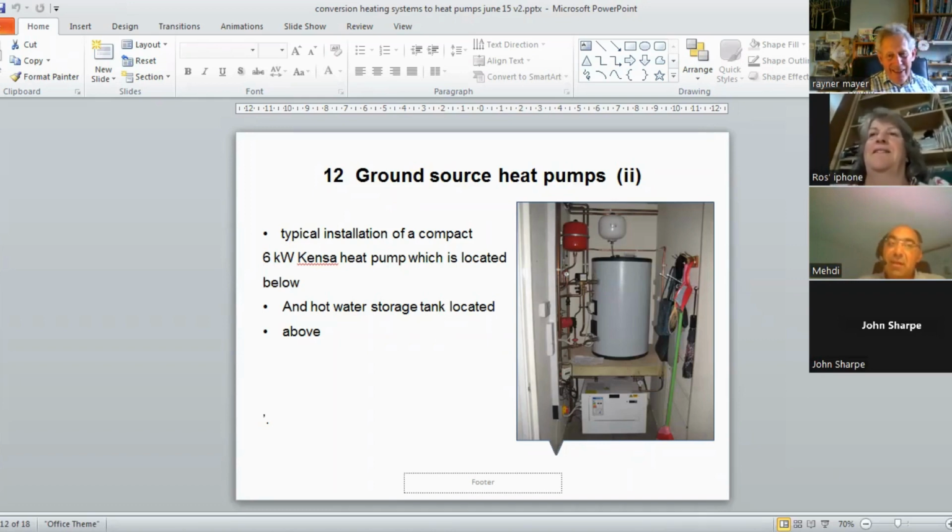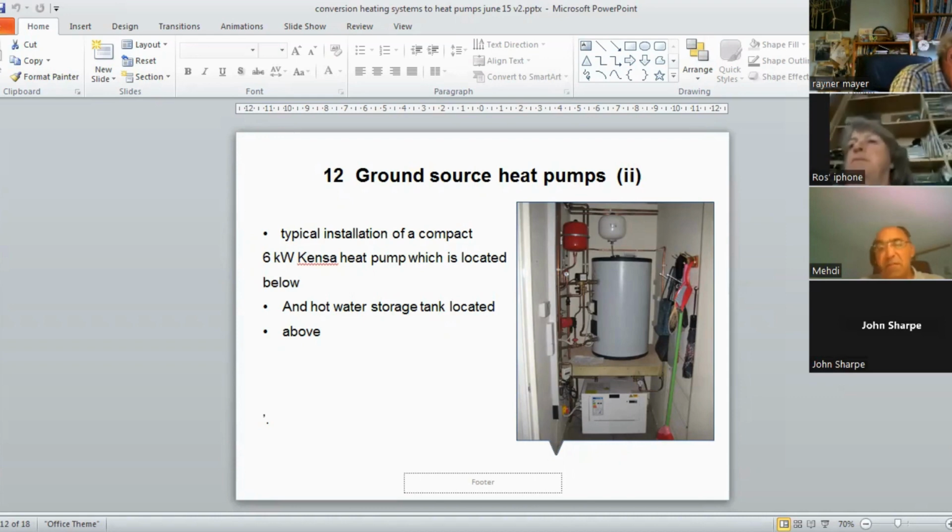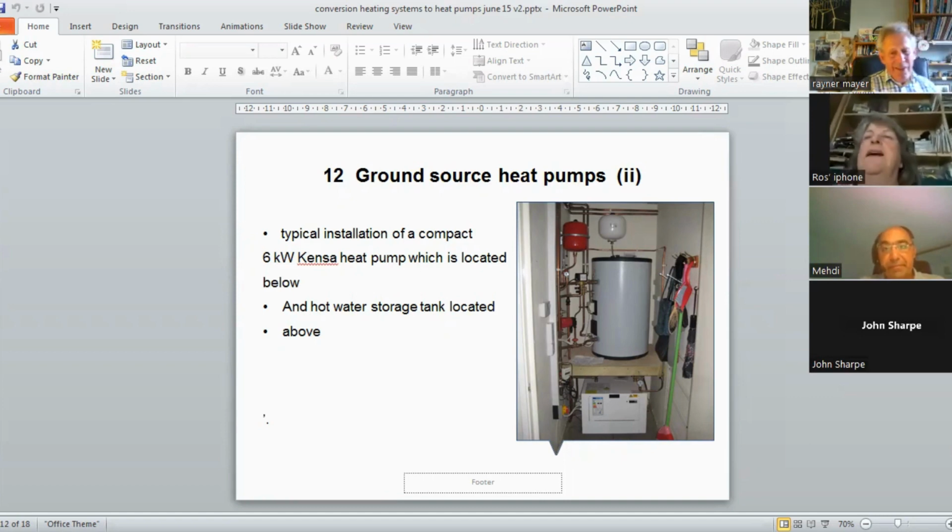If I can add something here, heat pump technology with the supply of heat in the range of maximum around 50 degrees C works very well with underfloor heating that doesn't need 70 degrees C. That's a very good design for heat distribution and heat generation: heat distribution by underfloor heating and heat generation by heat pump.